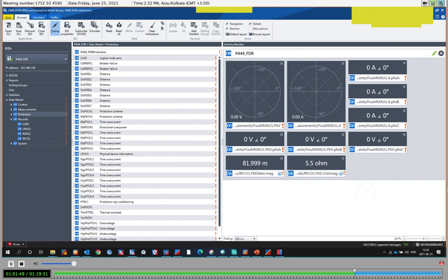Yes. Like if I have the publisher and subscriber IED both. Normally I see the goose coming from the publisher because the subscriber is not sending anything. But in addition, the subscriber has a logical node called LGOS, logical node for goose supervision, and IEDScout can read the value from there to see whether the subscriber received the value or not. So yes, we can check the published goose, talk to the subscriber, read the LGOS value, and understand whether the subscriber has received this goose or not.